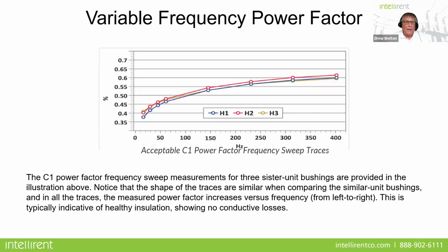Okay, now here we see a frequency trace, a C1 measurement, of sister bushings. All three bushings have the same geometric shape going from 10 to 400 hertz. They also have a lower power factor between that 10 and 60 hertz range. Now, that would indicate that we have no significant conductive losses. So you're relatively safe in assuming that there's dry insulation within the bushing.